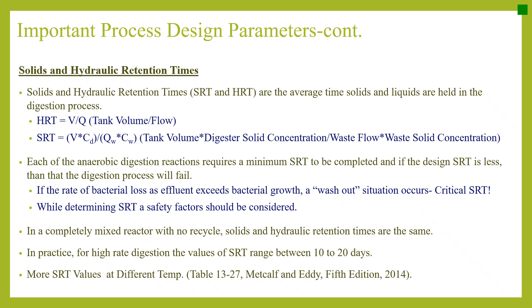While determining SRT, a safety factor is usually added to the design SRT. In a completely mixed reactor with no recycle, solid and hydraulic retention times are the same. In practice, for high-rate digestion the values of SRT range between 10 to 20 days, and more specific values at different temperatures are given in Table 13-27 of Metcalf and Eddy, 5th edition.